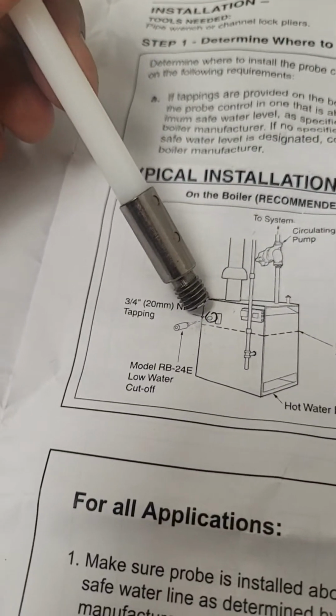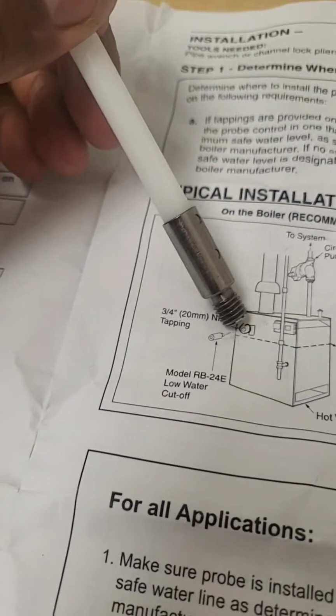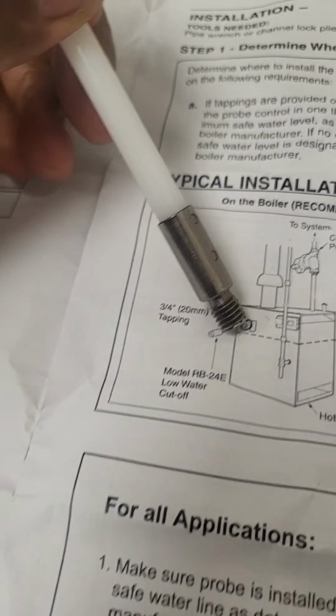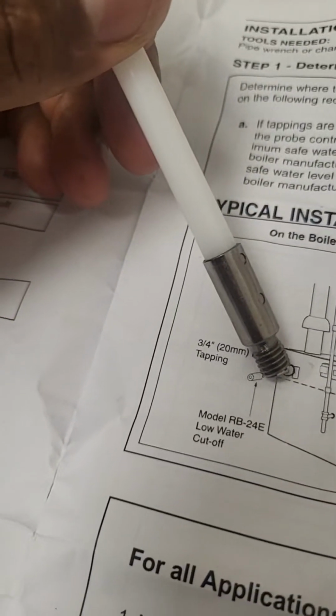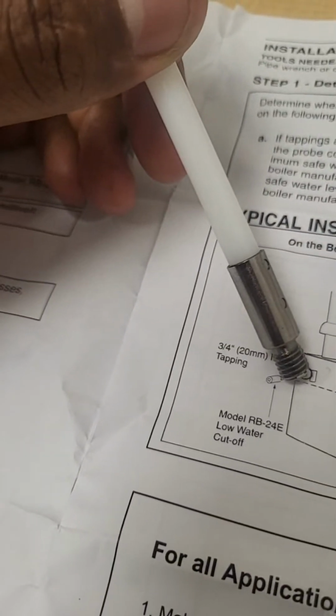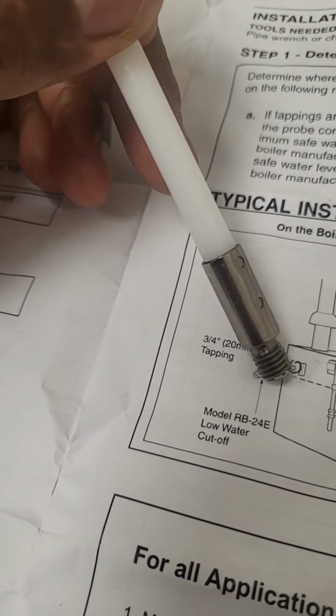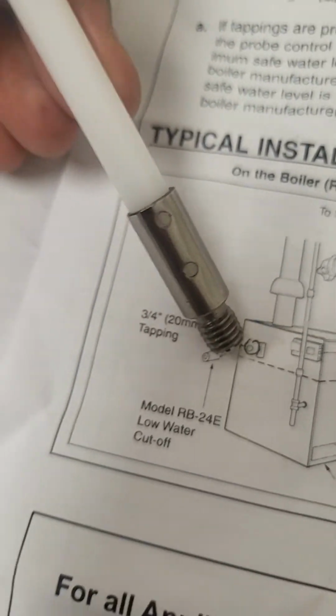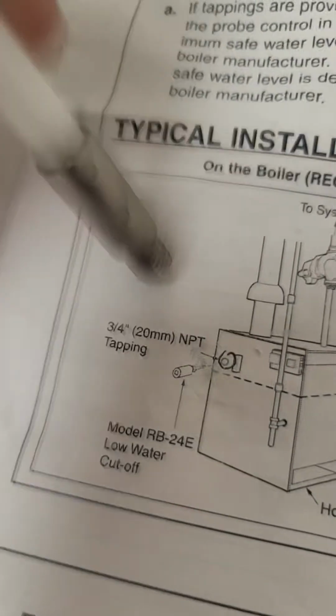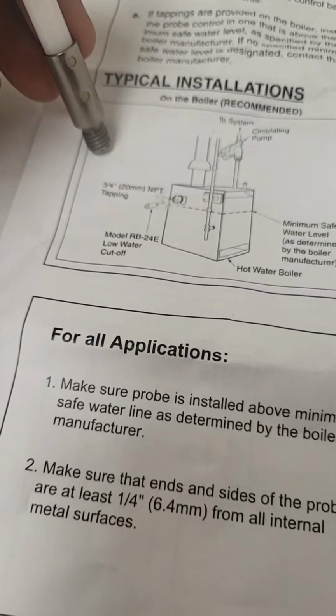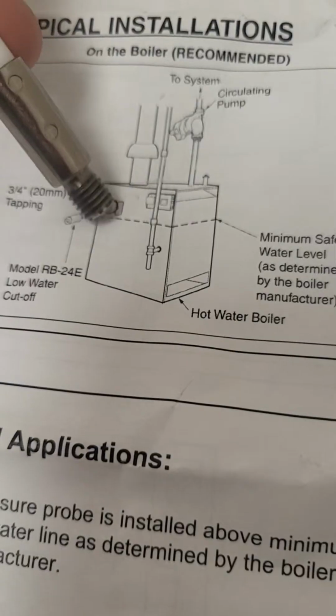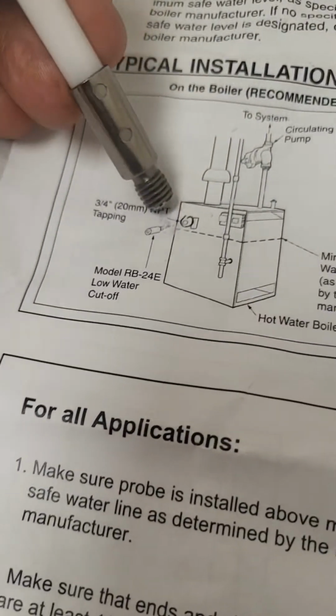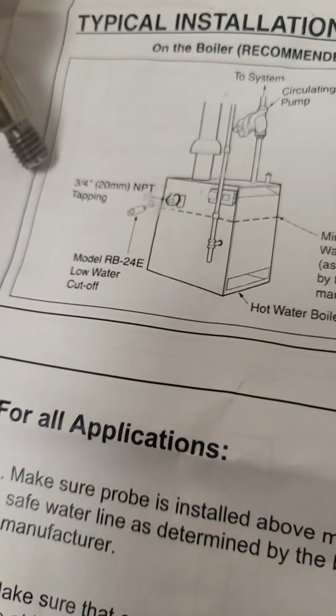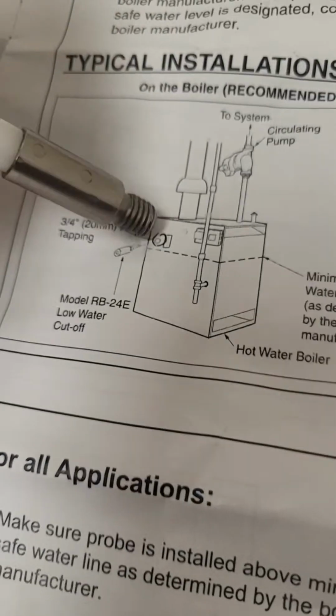This tapping could be rusted the hell over, and you can use your pipe wrench, whatever the case is. You plumber guys probably know about heating it up or chiseling it out, and I'm sure some of you have crazy methods of removing rounded out bits. Hats off to you, but personally I value my time. I'm not trying to spend three hours, unless I have to, trying to take out a rusted bit on the side of a boiler just to put in the low water cutoff.